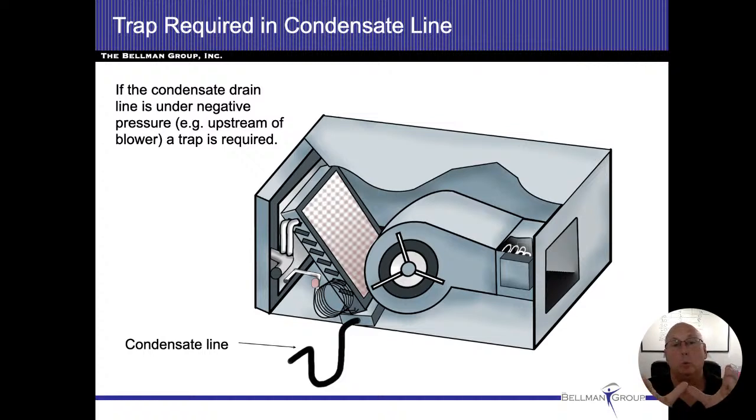Now, normal flow of air, we're never going to put our air conditioning coil before our gas forced air heat exchanger. All right. That just doesn't happen. In this drawing, they're showing this as an electric furnace. All right, so you can see the electric coils on the right side, then the blower fan, and then we have our slab coil before that. So the air is flowing from left to right.